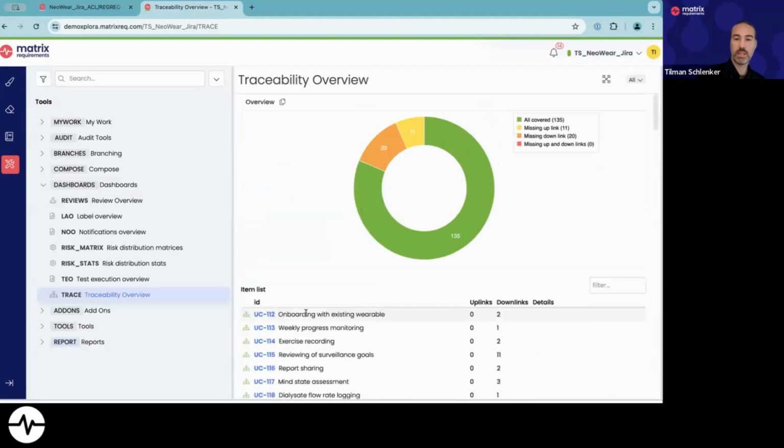And it's basically checking if these have been covered by verification tests, because in this case, we also have use cases in there. There's also validation tests. But basically, what the system helps you to do is to find gaps. Because one of the common things you'll do in the project is you'll find out there's a different requirement or different use case that you need to cover, or you added a new component to the system and you forget to link it up with test cases.